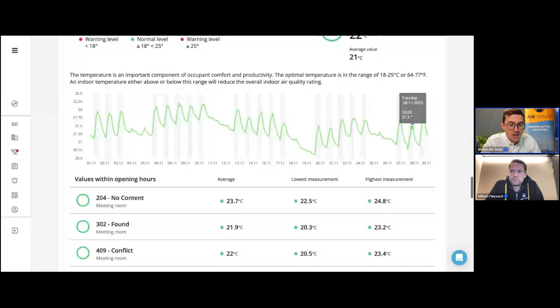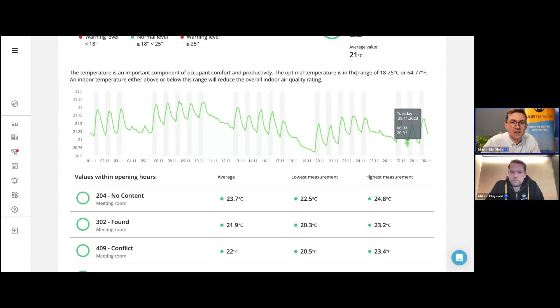It reduces at night and during the weekend when no people are present, and that's what you want to see. What I've seen often as an unhealthy sign is when it's flatlining, a flat constant temperature. That means your heating is not demand-controlled or adapting to actual usage, which might be an opportunity to optimize and save energy, particularly at night and on weekends.